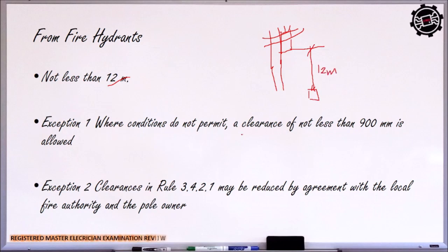No? So where conditions do not permit, a clearance of not less than 900 mm is allowed. So this is usually applicable if yung sa malapit na part ay hindi na talaga pwede na magkaroon ng 12 meters na clearance, but provided yung mismong paglalagyan ng equipment or the supporting structure itself is fire rated. Exception: may be reduced by agreement with the local fire authority. So kaya magkakaroon tayo ng mga equipment which is fire rated, fireproofing rated, or di kaya magkaroon ng spacing, tinatawag na firewall, between the equipment and the fire.